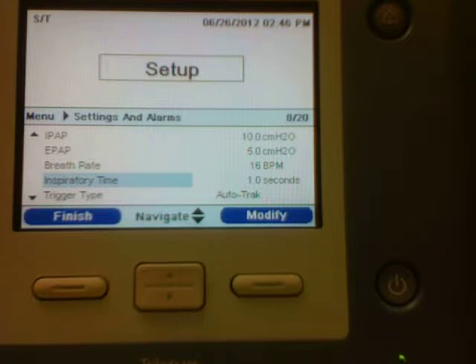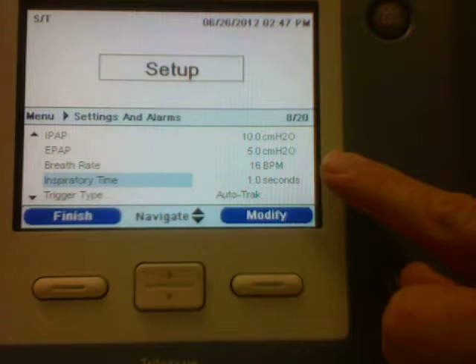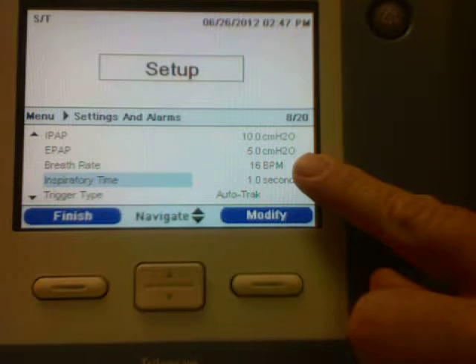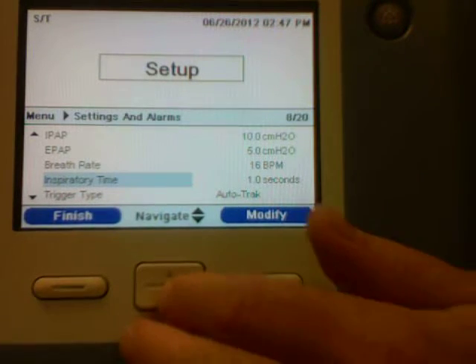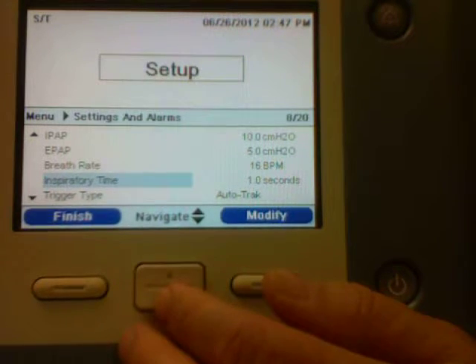Okay, so let's say you are ventilating your patient with a rate in this mode. What would you set your inspiratory time on? Well, I would recommend probably somewhere around 0.6 to 0.8, because if you look at it this way, 700 cc tidal volume delivered at 60 liters a minute would be about a 0.7 second inspiratory time. But again, you only need to worry about inspiratory time in terms of breaths delivered by the machine. If the patient's strictly breathing spontaneously, then that inspiratory time doesn't matter.